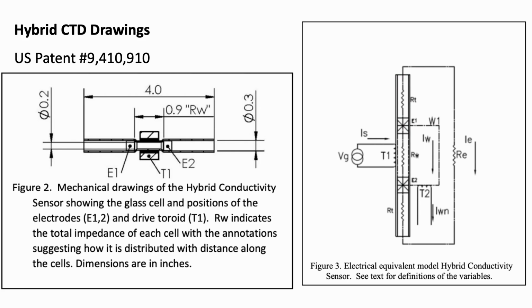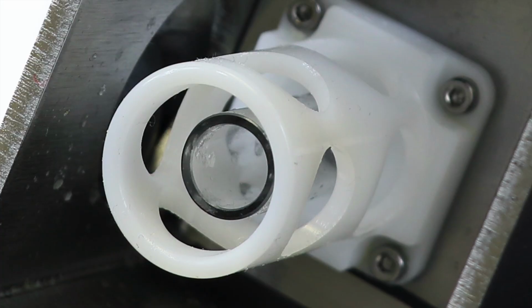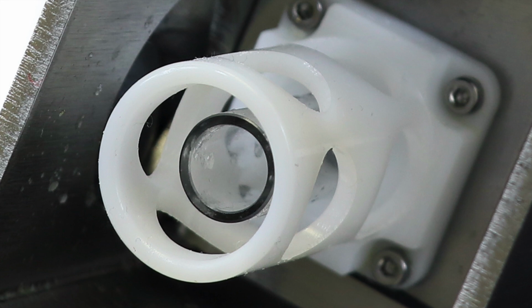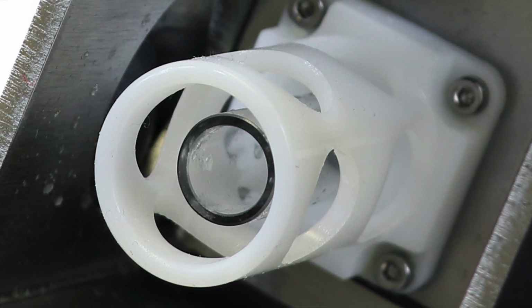We call our new patented design a hybrid CTD cell because it truly is. It is a closed field conductivity cell, which makes it similar to the Seabird cell. However, instead of having a third closed electrode across the middle, it uses an inductive drive, which is similar to inductive cells. Thus, it's a new patented hybrid conductivity cell that delivers the same accuracy that closed field cells can, but also has the ability to be free-flowing and have no need for a pump.